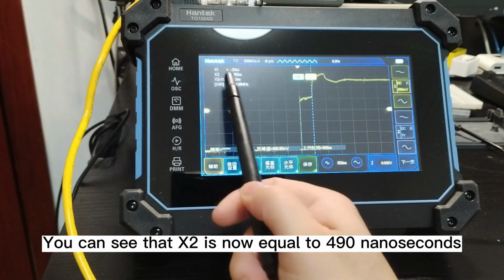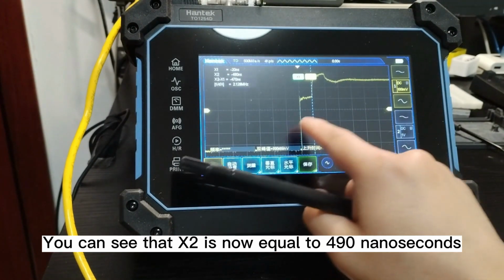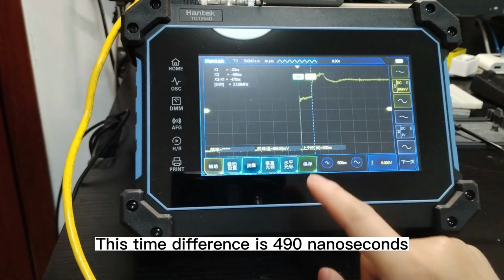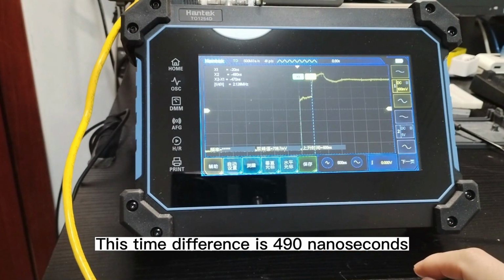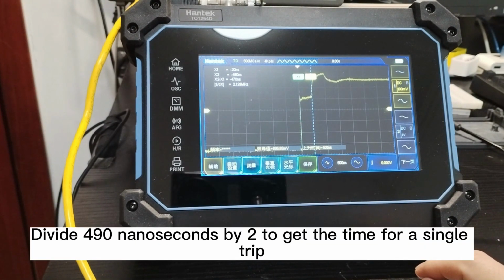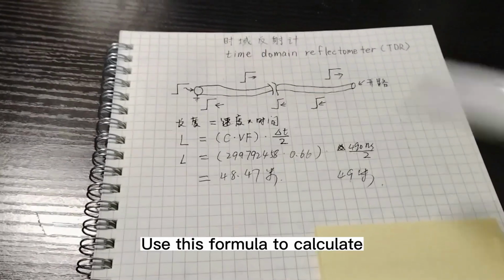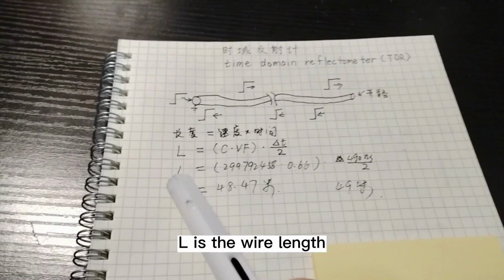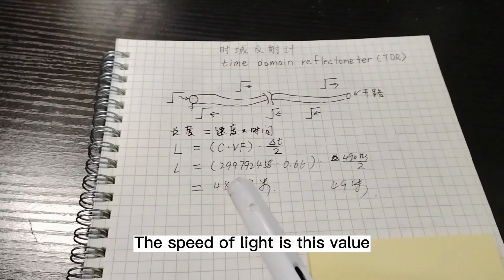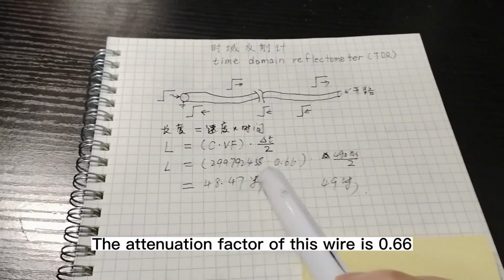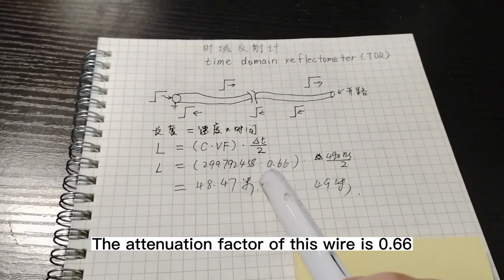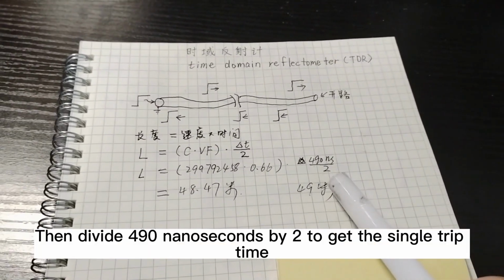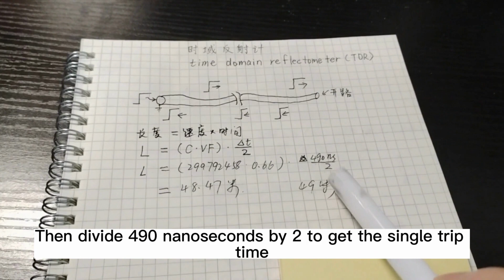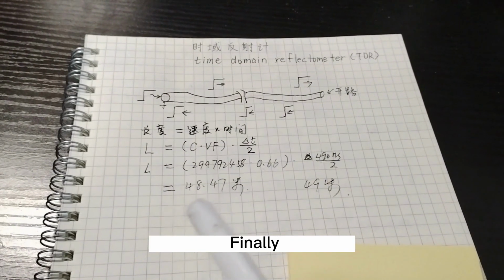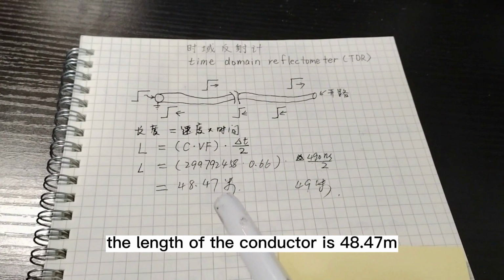You can see that x2 is now equal to 490 nanoseconds. This time difference is 490 nanoseconds. Divide 490 nanoseconds by 2 to get the time for a single trip. Let's calculate. Use this formula to calculate. L is the wire length. The speed of light is this value. The attenuation factor of this wire is 0.66. Then divide 490 nanoseconds by 2 to get the single trip time. Finally, the length of the conductor is 48.47 m.